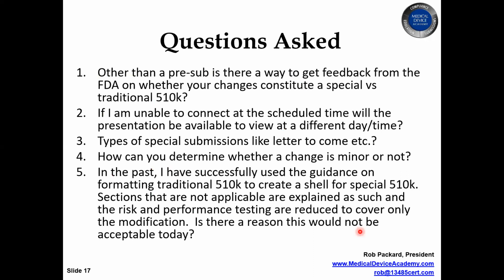If you had to do new verification testing that was never required before, instead of repeating existing verification protocols, that might be a good hint this isn't minor, because you've identified a new risk that required a new test. Now, however, if in the past they didn't require that testing and now this is a new requirement, that might be a reason why you have a new test.